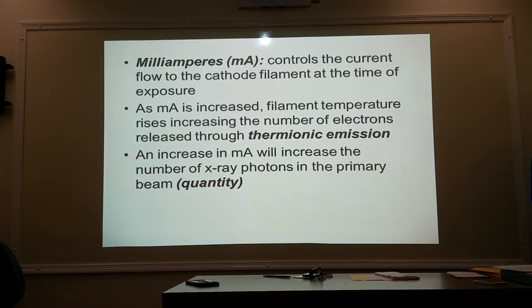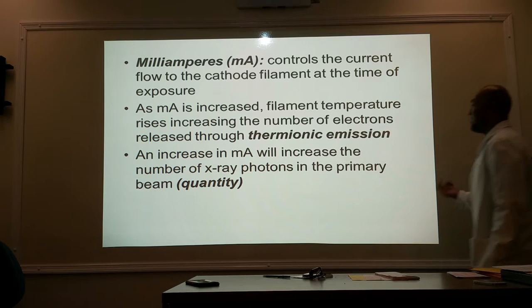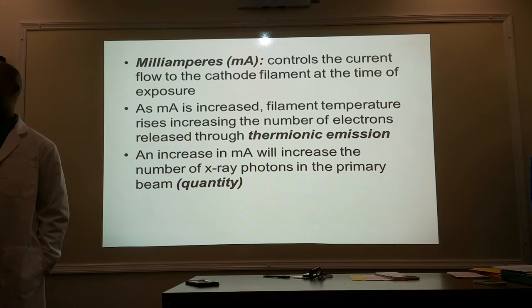The number of electrons is also related to the number of x-ray photons that we produce. So the more electrons that we boil off, the more x-ray photons we are producing, which is also controlling patient exposure. An increase in MA will increase the number of x-ray photons in the primary beam. It controls quantity, not quality — the amount, the number.